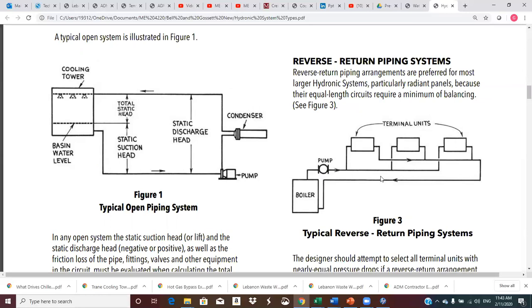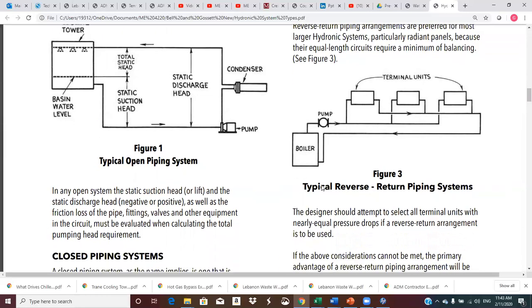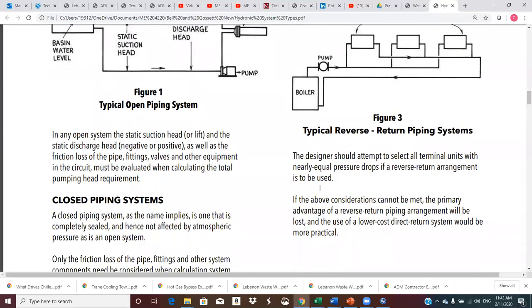We have kind of an intermediate path here, and we have an intermediate path on the return. And I have a long supply pipe, but relatively short on the return. So that's what the return or reverse return system does. Designers should attempt to select all terminal units with equal or near equal pressure drops if a reverse return arrangement is used.